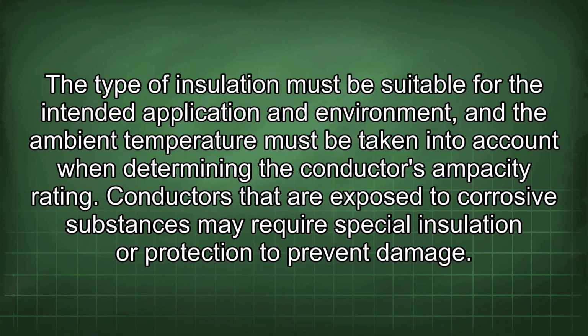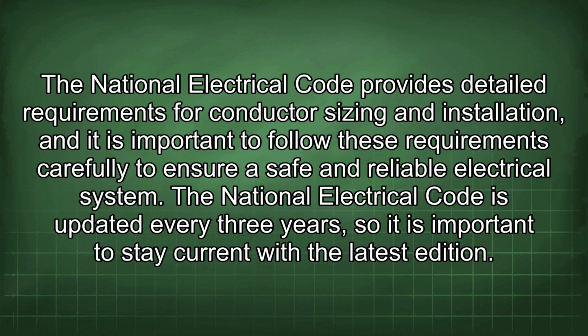The type of insulation must be suitable for the intended application and environment, and the ambient temperature must be taken into account when determining the conductor's ampacity rating. Conductors that are exposed to corrosive substances may require special insulation or protection to prevent damage. The National Electrical Code provides detailed requirements for conductor sizing and installation, and it is important to follow these requirements carefully to ensure a safe and reliable electrical system.